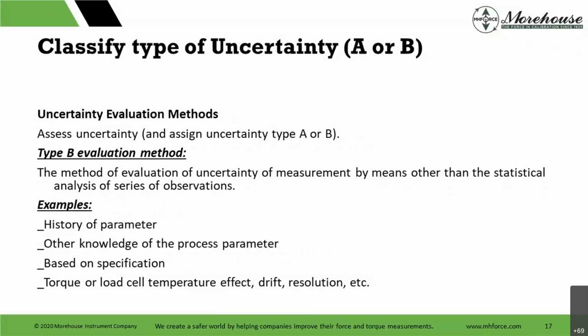The other method is type B. Method of evaluation of uncertainty of measurement by means other than the statistical analysis of a series of observations. So here we're talking about things like history of the parameter, other knowledge or process parameters, based on a specification, torque or load cell temperature effect. Maybe we're talking about the temperature effect of a load cell. Per 1 degree Celsius, I have an additional error of 0.0015% with a Morehouse shear web load cell.